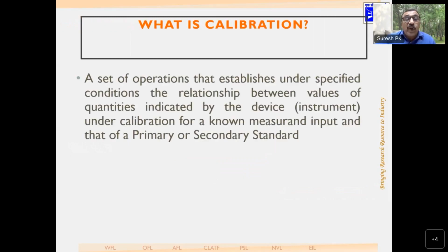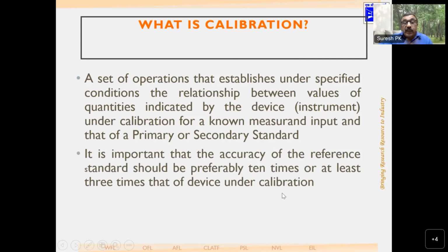So now what is calibration? It's a set of operations that establishes, under specific conditions, the relation between values of quantities indicated by the device under calibration for a known measurand input. That is, if you give an input, the instrument will show some reading. That input is supposed to be the true value and the output is the indication of the reading, and there may be some error due to many reasons. It is important that the accuracy of the reference standard should preferably be 10 times, or at least 3 times, better than the device under calibration. Otherwise, you will not be able to determine the accuracy of the instrument under calibration.